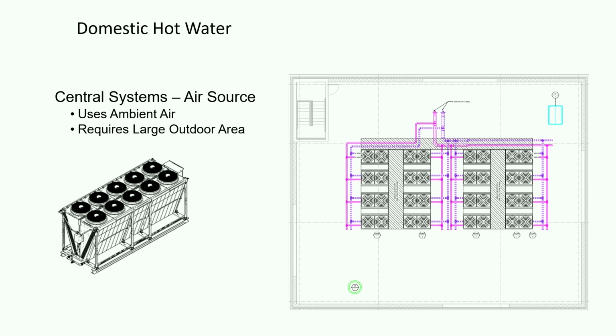So one thing that you're gonna have to keep in mind, if you're gonna use wastewater as a thermal asset, where does all your wastewater exit the building? At the bottom. Generally in high-rise buildings, all your domestic hot water plant equipment is on the roof. So now if I'm going to put any heat into my domestic hot water, I may have to completely reverse my domestic hot water piping from being fed from the top to the bottom. And how does that impact pumps, pressure, a lot of different things. So if you're going to incorporate some of those technologies, it may completely change your design on where you're going to put equipment and how you pipe the building and what you would normally do. So you got to know that stuff pretty early on, okay?